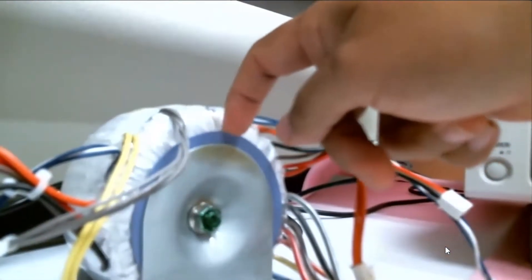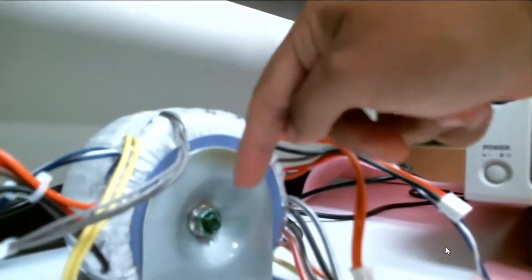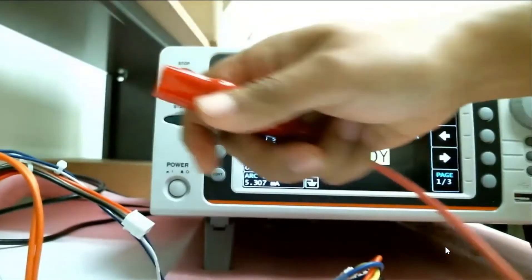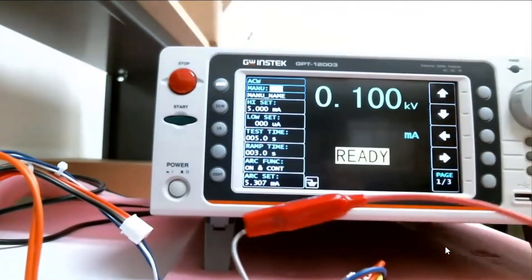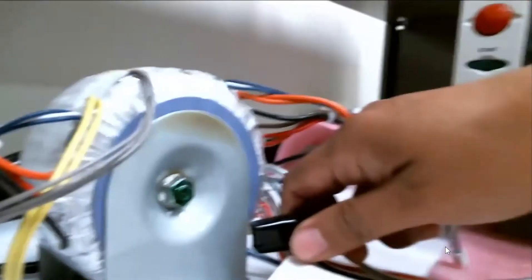And it's mounted onto a piece of metal chassis, right? Obviously there's some insulation here to protect from the arcing from this point to this point. So how this test would run, we would connect one of our voltage terminals, and I'll just use one of these windings as an example to one of the windings here. And our return lead or ground reference to the chassis itself here.